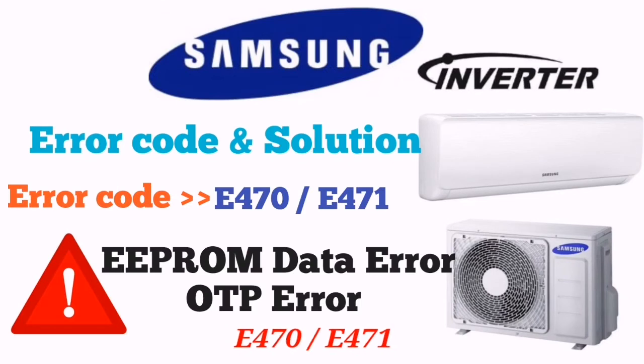When you see error E470 or E471, or LED 1 is off, LED 2 is on and LED 3 is off, or LED 1 is on, LED 2 is off and LED 3 is blinking, at that time you can understand it's an EEPROM data error or OTP error. At that time you have to do one thing.